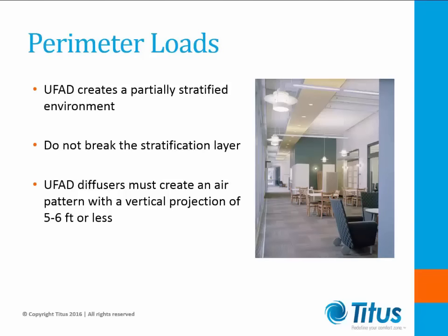Before we can address perimeter heating loads, it's important to understand what we need to do from an air distribution perspective. Our UFAD system is creating limited stratification in the occupied zone, taking advantage of the natural buoyancy of interior heat from people, office equipment, and lighting to rise and leave the room. Therefore, it's critical that any perimeter heating solution must not interfere with the interior system. Any UFAD outlets located on perimeters need to create a vertical air pattern that provides coverage on exterior walls and glass, but the vertical projection should never exceed the height of the occupied zone. If the perimeter outlets break through the stratification layer, heat and pollutants are likely to be drawn back into the occupied zone, defeating the purpose of the UFAD system.